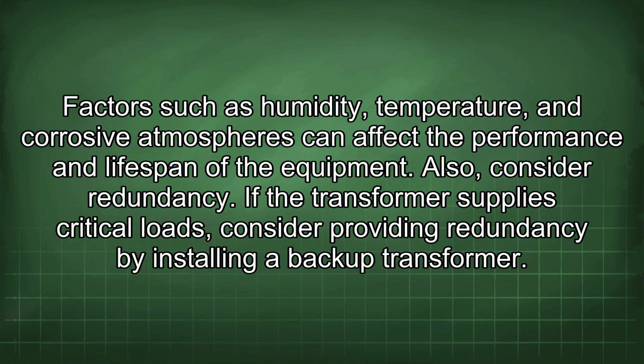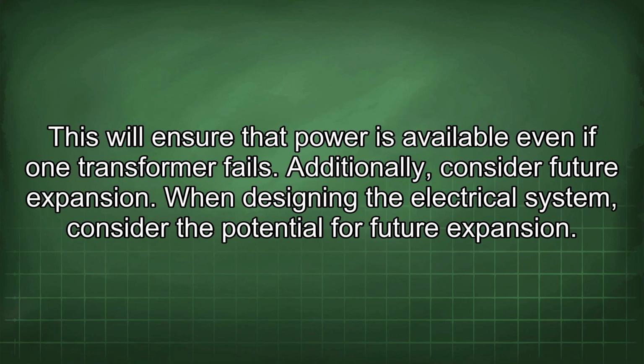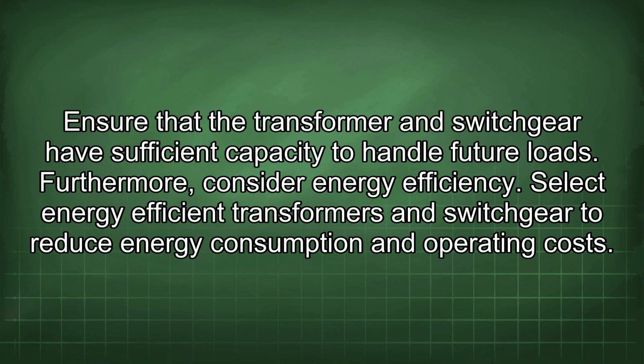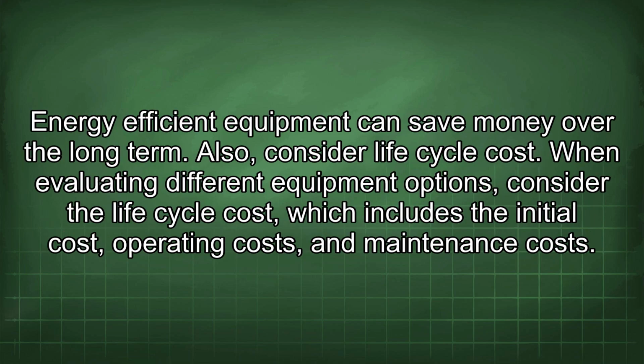Also, consider redundancy. If the transformer supplies critical loads, consider providing redundancy by installing a backup transformer. This will ensure that power is available even if one transformer fails. Additionally, consider future expansion. When designing the electrical system, consider the potential for future expansion. Ensure that the transformer and switchgear have sufficient capacity to handle future loads. Furthermore, consider energy efficiency. Select energy-efficient transformers and switchgear to reduce energy consumption and operating costs. Energy-efficient equipment can save money over the long term.